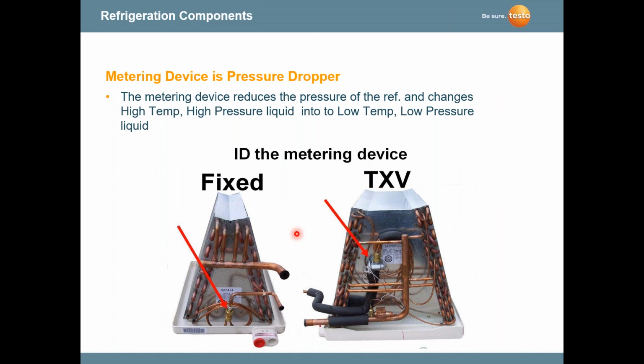We also have a metering device, and these metering devices can be fixed or they can be TXV. A lot of them are TXV today. And as we look at a compressor, this increasing pressure, this metering device is a pressure dropper. It's going to reduce the pressure before it gets to the coil. Less heat in the refrigerant. So in this case, we've got hot distribution air going over the coil, which is a little colder or has less heat, and we have a transfer of heat from the distribution air to the refrigerant. In this case, the opposite of a condensing unit.